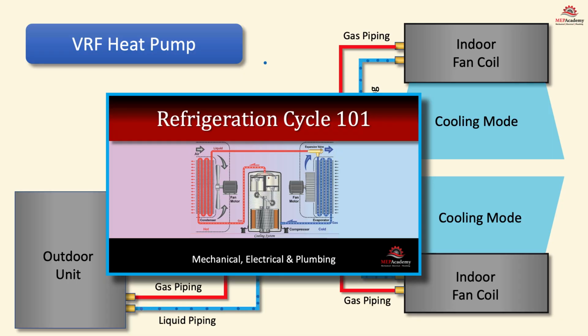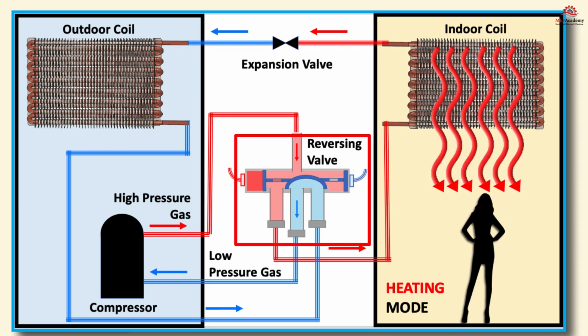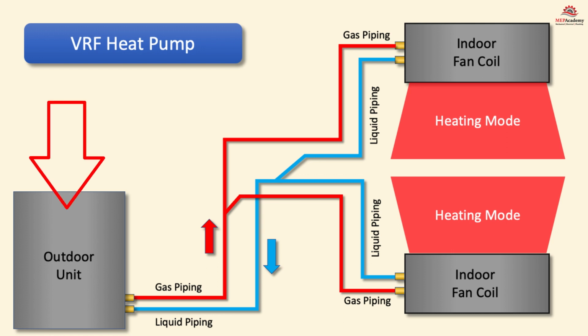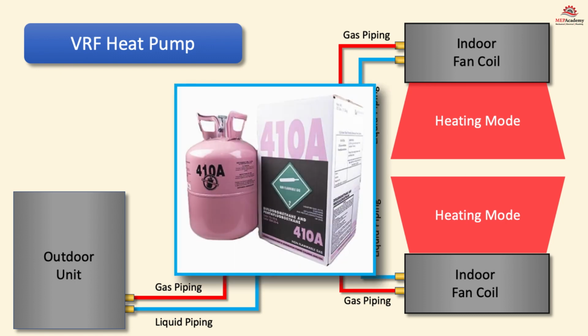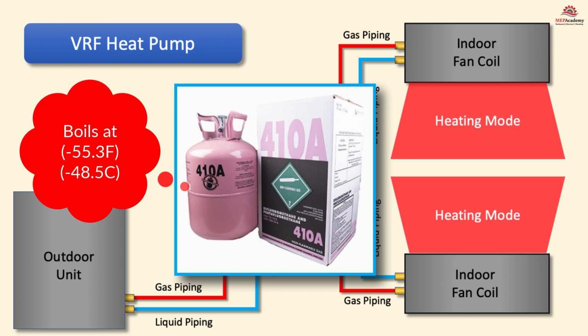The heat pump has a reversing valve which changes the direction of flow to each of the two coils. In heating mode, the indoor coil now becomes the outdoor coil. So during the cold winter, the outdoor coil acts as the evaporator and absorbs heat from the cold outdoor air. You're probably wondering how there is any heat in the cold winter air. Well, this is the magic of refrigerants, as R410A is commonly used in VRF systems, and this refrigerant boils at negative 55.3 degrees Fahrenheit, minus 48.5 Celsius.